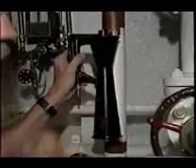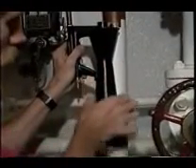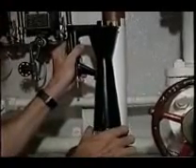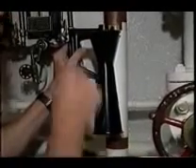Now what a venturi is, is a restriction in the flow. What I do is I start off with a restriction, typically about 22 degrees, to a straight section of the pipe, and then a slow expansion back to the original pipe diameter. The pressure is measured before the venturi and at the constricted region.